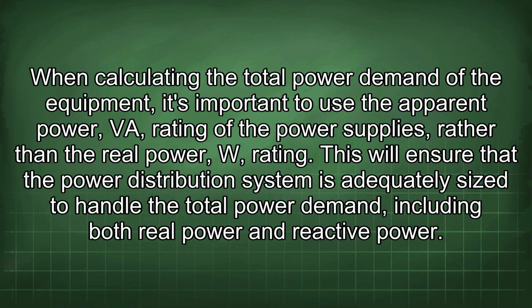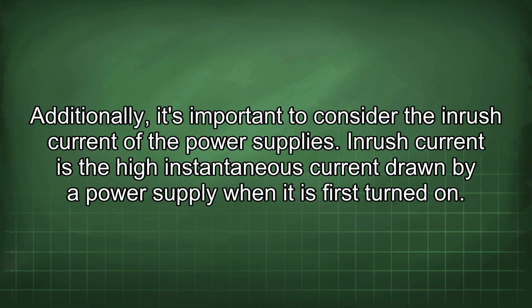When calculating the total power demand of the equipment, it's important to use the apparent power (VA) rating of the power supplies rather than the real power (W) rating. This will ensure that the power distribution system is adequately sized to handle the total power demand, including both real power and reactive power. Additionally, it's important to consider the inrush current of the power supplies.